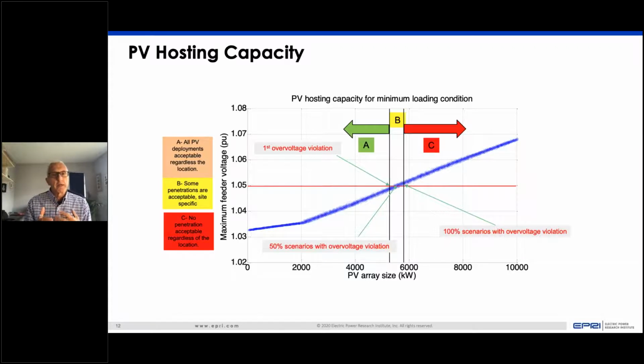At some point, that voltage rise exceeds our limits, which might be 105%. That illustrates where, for the current design, without implementing new voltage control measures, which might include the characteristics of the inverter itself, we can estimate how much PV we can put on that distribution system without causing problems, and maybe the interconnection evaluations are much simpler up to that point.